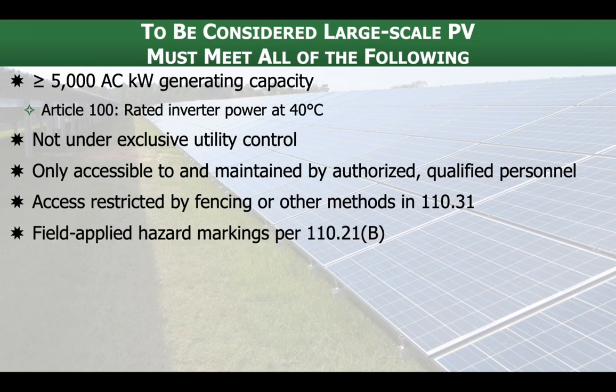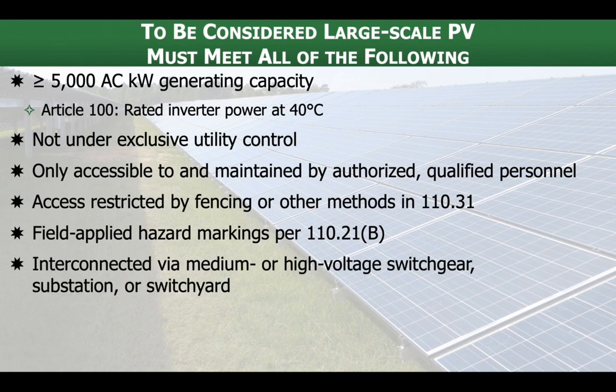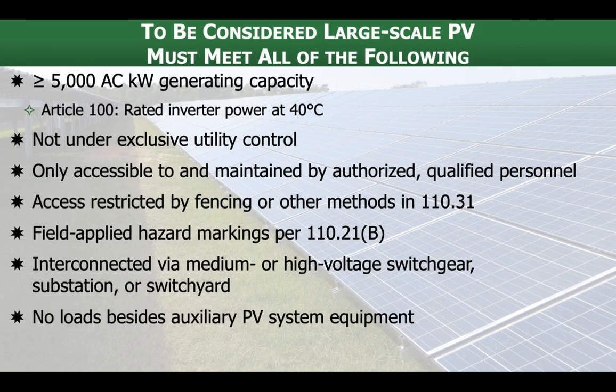Field applied hazard markings are required. We talked about 110.21(B) in other parts of this course. No differences there. The system, and here's a difference, is only interconnected to the grid via medium or high voltage. There's no utility service associated with the building or anything like that. This is direct to the utility at thousands of volts, tens of thousands of volts, through some sort of medium or high voltage switchgear, substation, or switch yard. There's no loads. Now, there might be loads that are part of the PV system. These could be things like security systems, lighting, convenience outlets, all of those sort of things that exist because the system exists, but we're not putting the system in to serve loads directly. Of course, once the power gets onto the utility grid, that's exactly what it's going to do, but that is separate from the PV system itself.